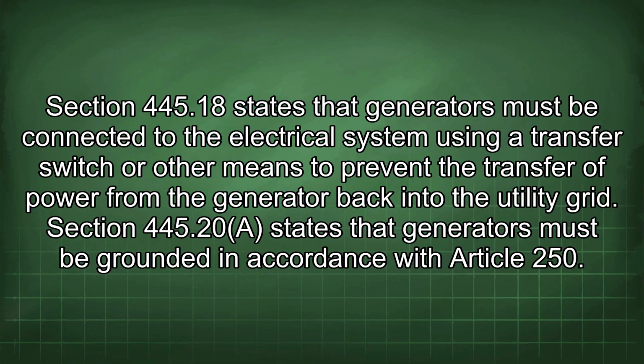Section 445.18 states that generators must be connected to the electrical system using a transfer switch or other means to prevent the transfer of power from the generator back into the utility grid. Section 445.20 states that generators must be grounded in accordance with Article 250.